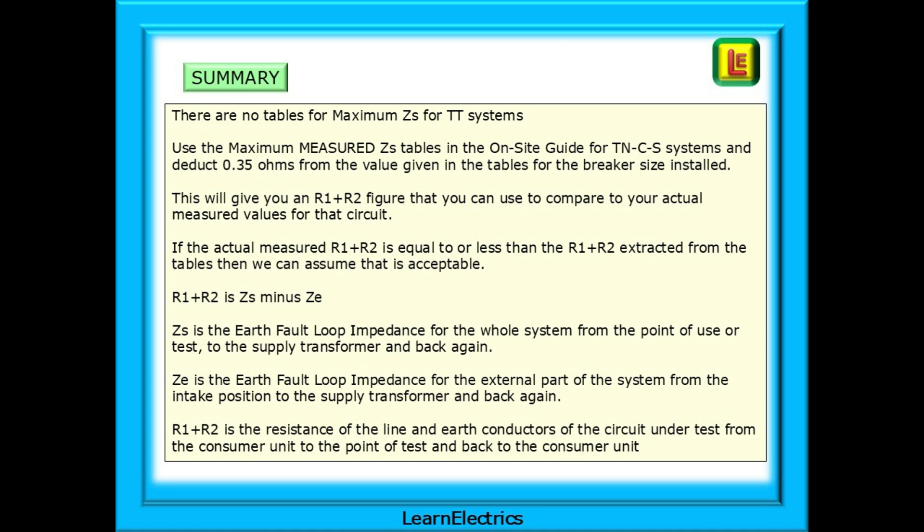And that is how I evaluate and confirm the internal wiring of a TT dwelling, a quick and easy method to give you peace of mind that this part of your own work is okay. There are no tables for maximum ZS for TT systems. Use the maximum measured ZS tables in the on-site guide for TNCS systems and deduct 0.35 ohms from the value given in the tables for the breaker that is installed. This will give you an R1 plus R2 figure that you can use to compare to your actual measured values for that circuit. If the actual measured R1 plus R2 is equal to or less than the R1 plus R2 extracted from the tables, then we can assume that the circuit values are acceptable.